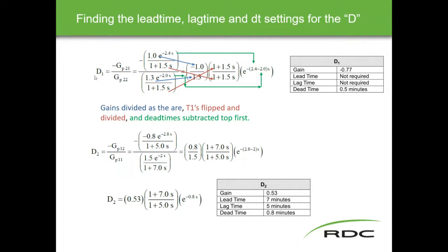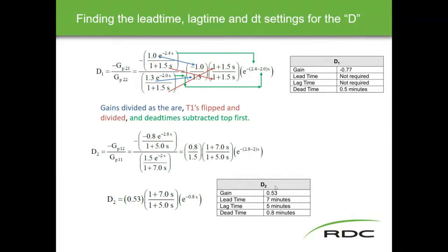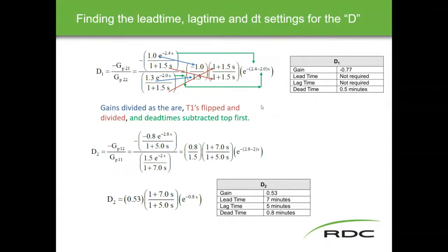The D1 formula is this formula; the decoupler 2 formula is this formula. The only difference is the combination of process variables and controllers used. So 0.8 over 1.5 here, with 1 plus 7 on top, 1 plus 5 on the bottom, and 2.8 minus 2 gives us the dead time. Our gain is the 0.53 value, the lead time is the top value, the lag time is the bottom value, and the dead time is this value. These ultimately become the settings put into decoupler two and decoupler one.